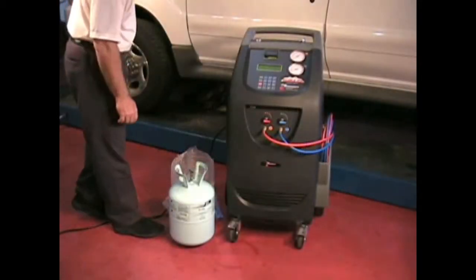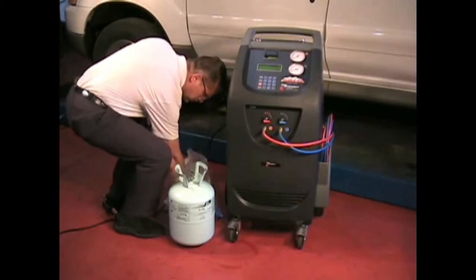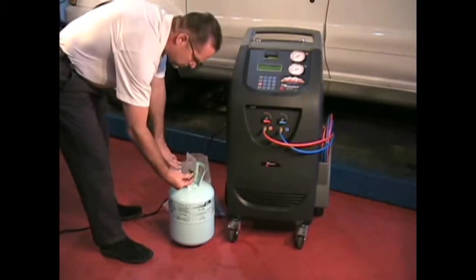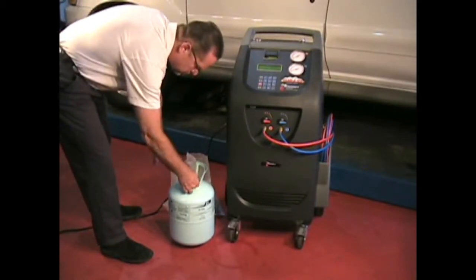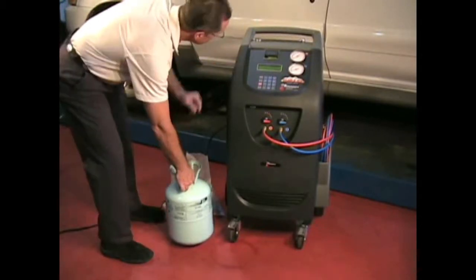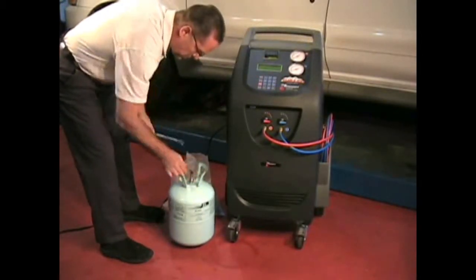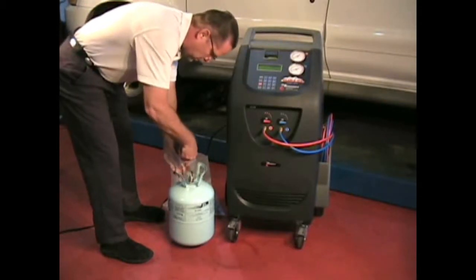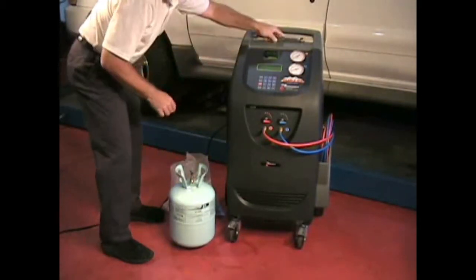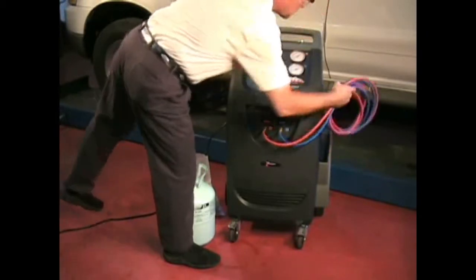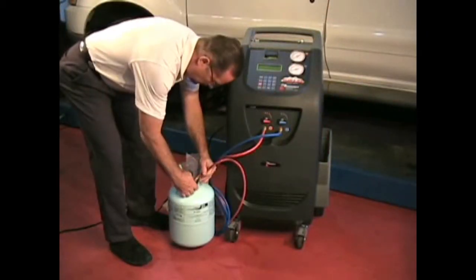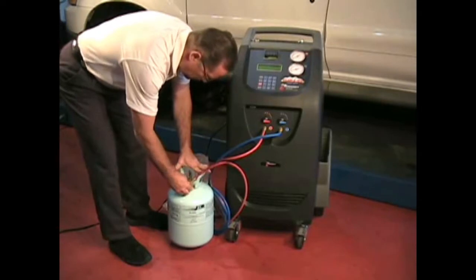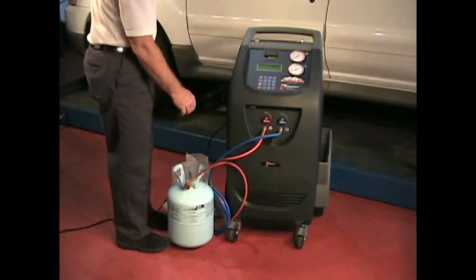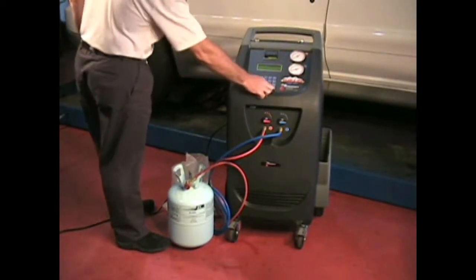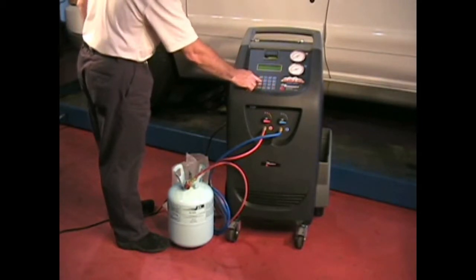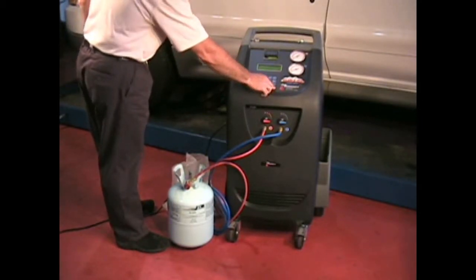Our next step of setup is to fill the internal bottle with R134A. Locate and install the Virgin tank adapter that is supplied with your machine onto the Virgin R134A tank. Connect the high side coupler to the adapter. Now arrow down to Next Menu and press Enter. Arrow to Bottle Filling and press Enter.